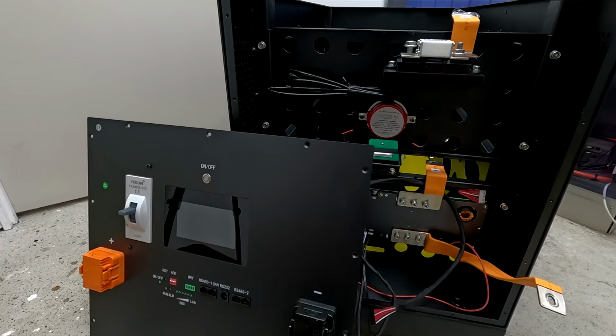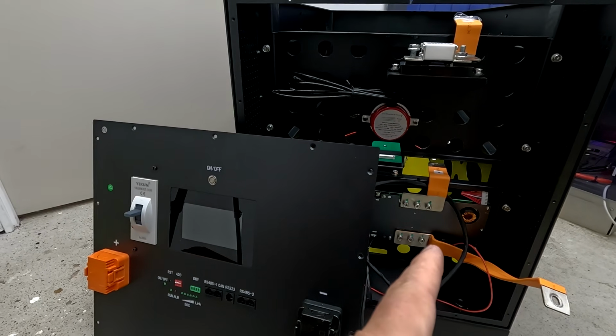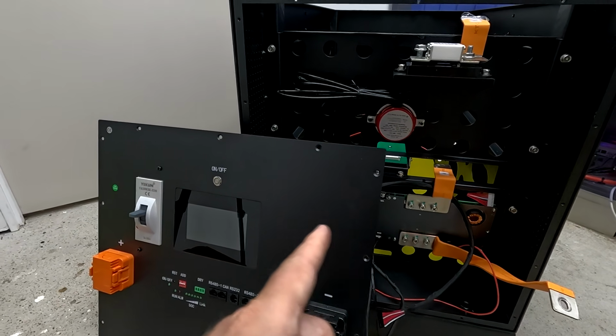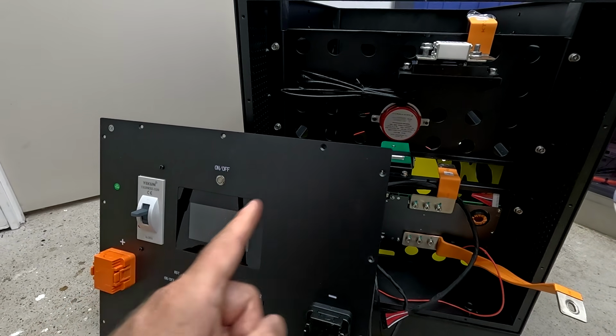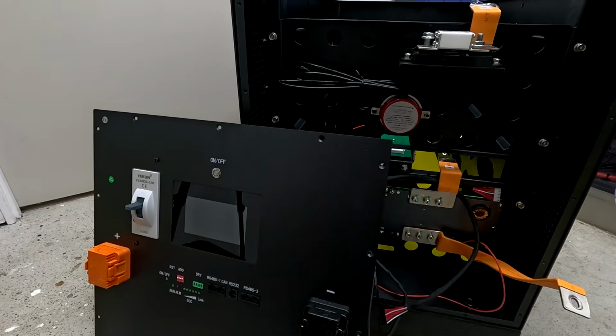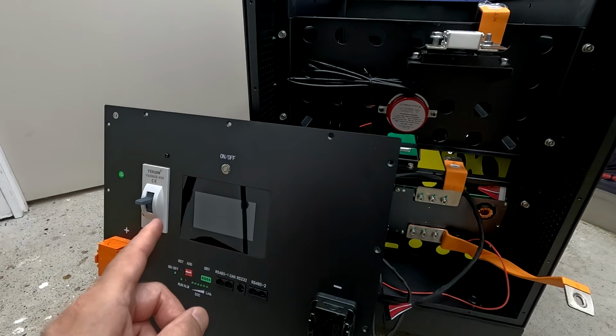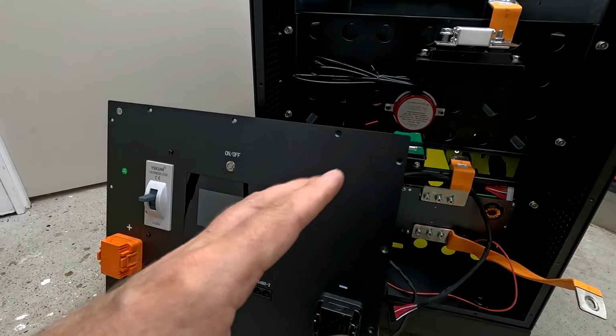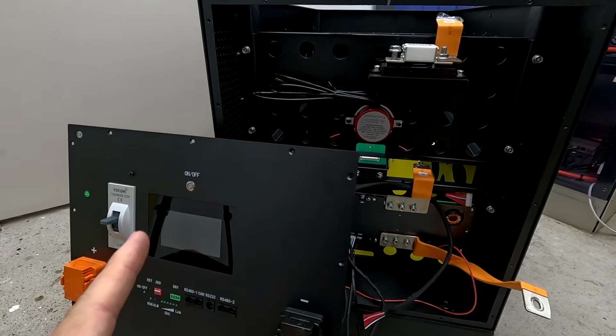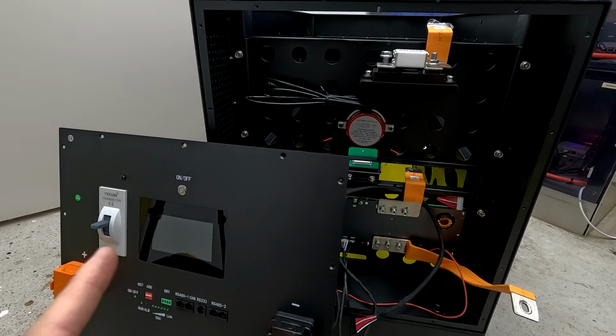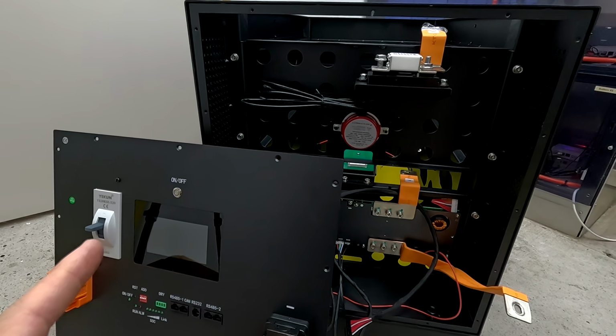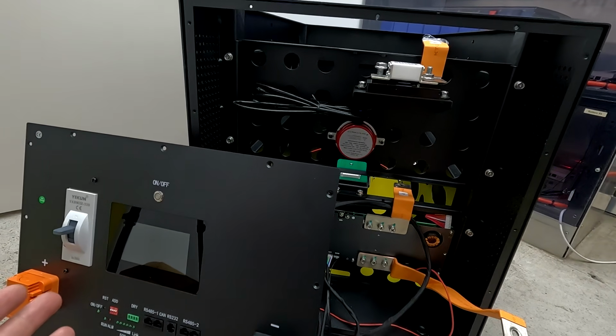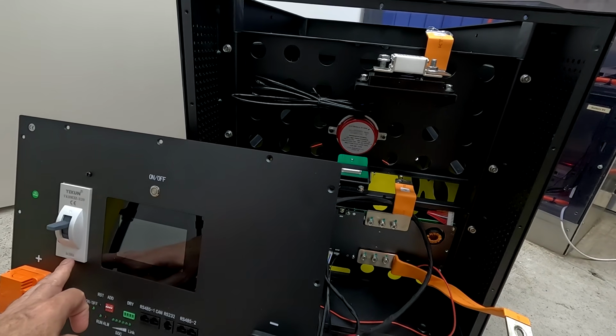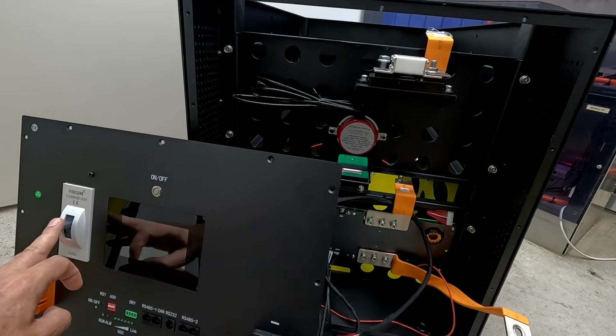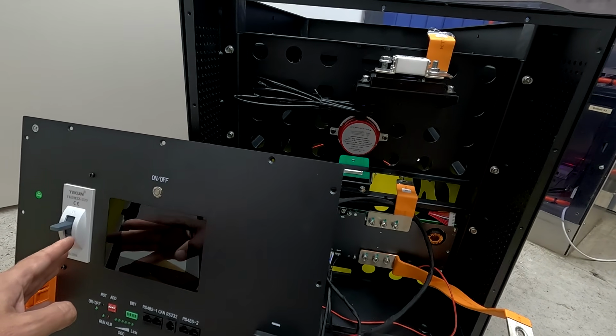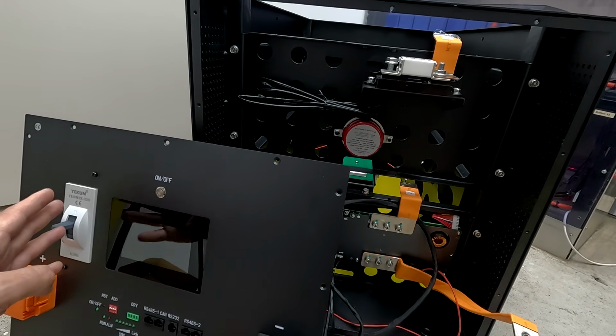And then we've got the selection of safety equipment here. We have a 300 amp BMS, a 300 amp circuit breaker, and a 300 amp fuse. Usually if you have a fuse and a circuit breaker, they should be staggered, because the fuse and circuit breaker have different characteristics. The circuit breaker is more a long-term safety device, meaning with our current we can go over 300 amps for quite a while until it trips. It needs to heat up first, and then at some stage it will trigger depending on the trigger curve.